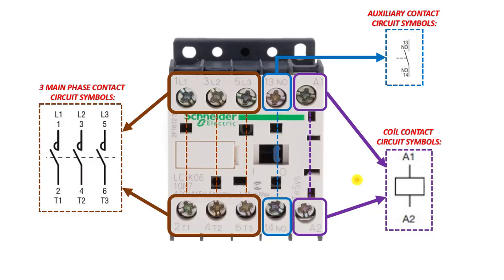The circuit symbol for the coil is shown on the right. The basic working principle of the contactor is: when we give the necessary voltage to the coil, the three main contacts and one auxiliary contact — which are normally open — become closed. When the required voltage is applied to A1 and A2, all contacts close and the connected loads start working.